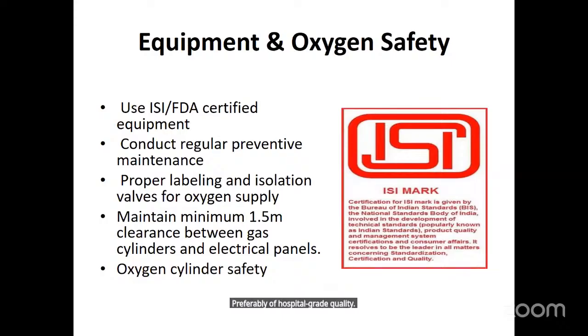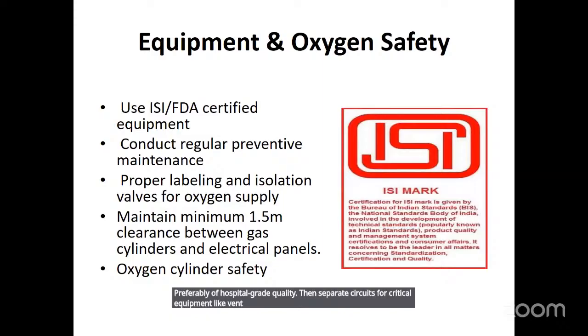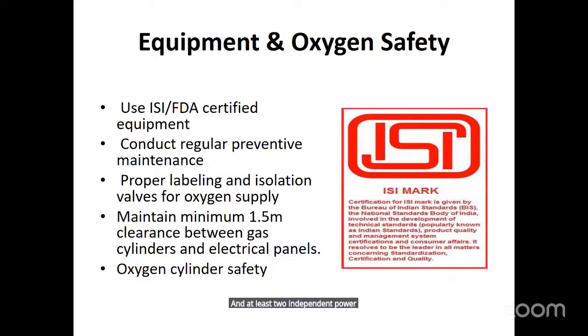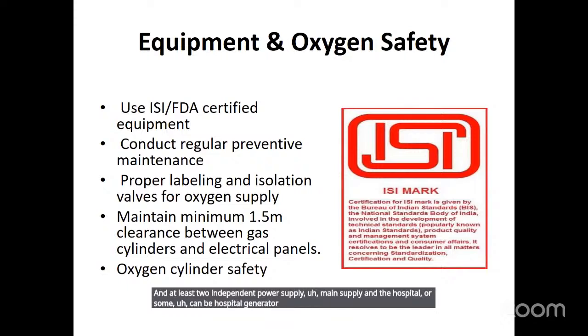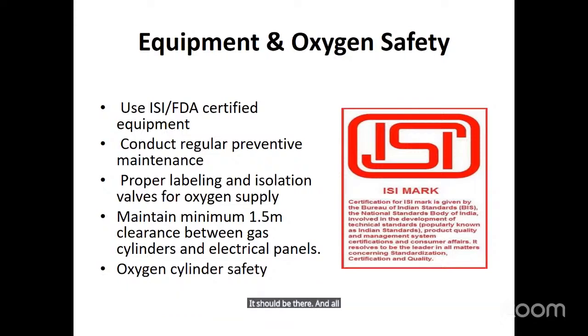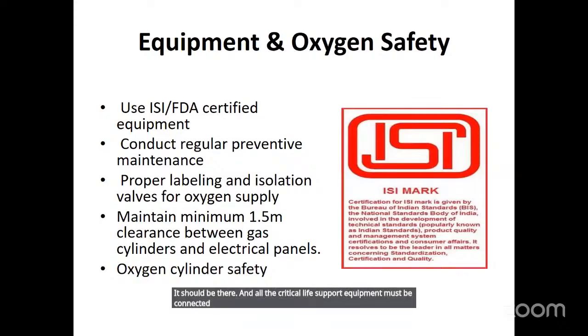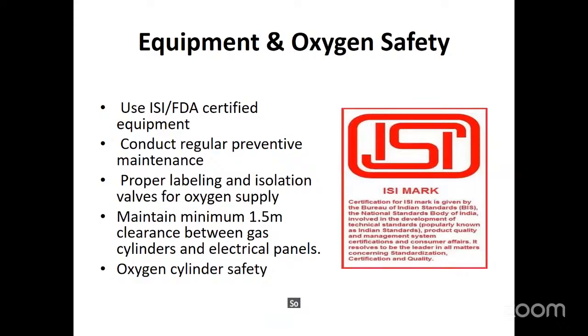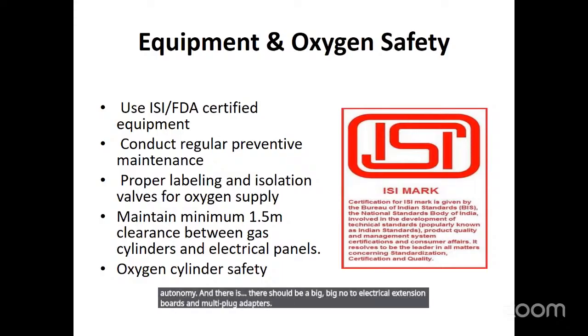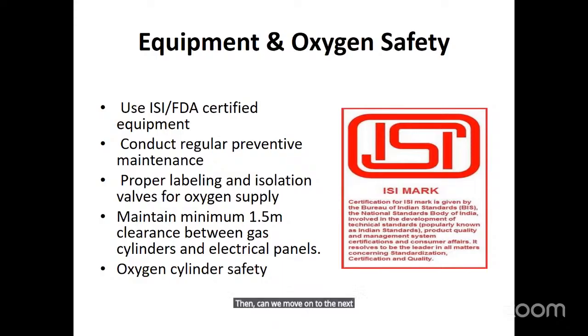Then separate circuits for critical equipment like ventilators and CPAP, and non-critical load, should be there. And at least 2 independent power supplies, the main supply and the hospital generator or UPS backup, should be there. And all the critical life support equipment must be connected to the UPS or inverter system, so that in case of fire, if there is a shutdown of electricity, there should be at least 30 to 60 minutes of autonomy. And there should be a big no to electrical extension boards and multi-plug adapters. Then can we move on to the next slide, please, sir?